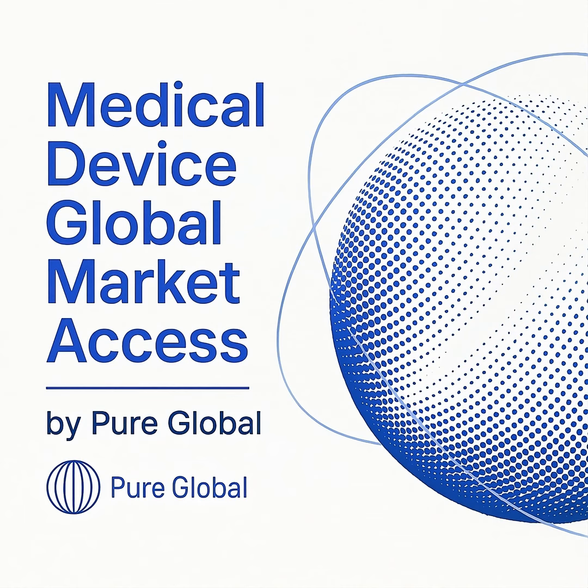more predictable regulatory environment. The classification of a medical device is determined by a set of rules outlined in HSA's guidance documents. These rules consider several key factors: the intended purpose of the device, how long it remains in contact with the human body, its degree of invasiveness, and whether it is an active device that relies on a source of energy. For example, a non-invasive device intended for transient use will naturally fall into a lower risk class than an implantable device intended for long-term critical cardiovascular support.